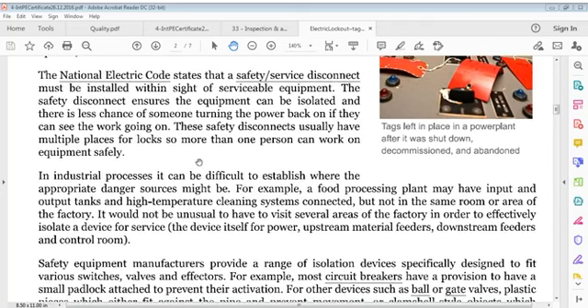The National Electric Code states that a safety service disconnect must be installed within sight of serviceable equipment. The safety disconnect ensures equipment can be isolated, and there is less chance of someone turning power back on if they can see work going on. These safety disconnects usually have multiple places for locks, so more than one person can work on the equipment safely.